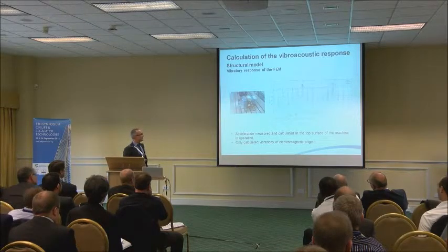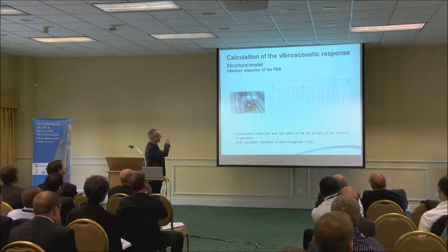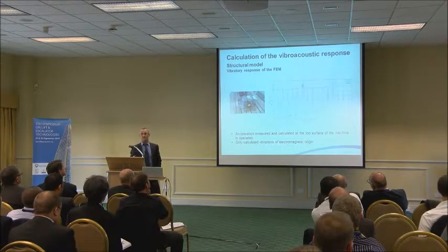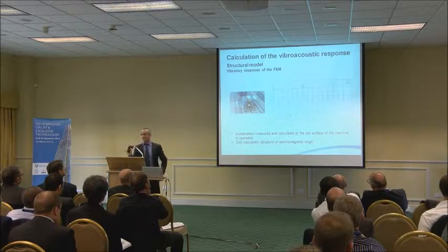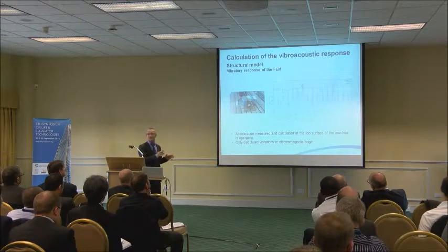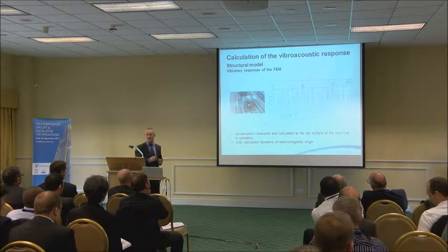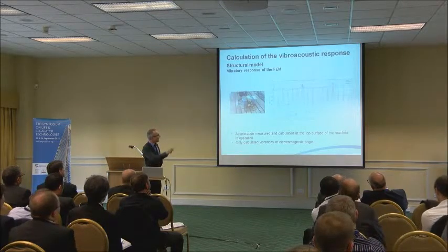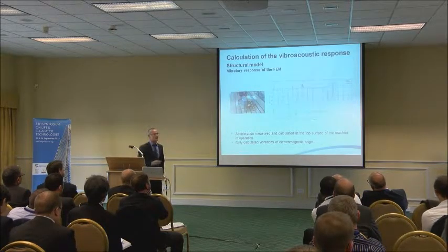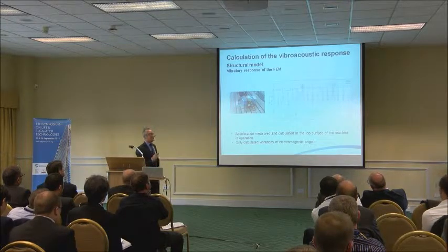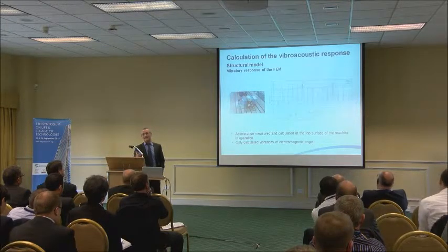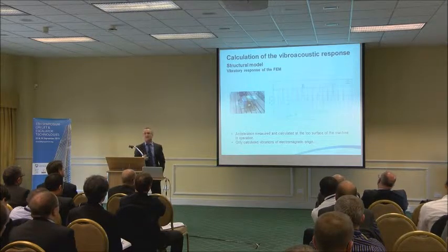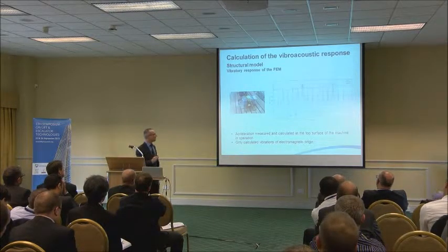And we see the picture there, where we see in blue the measured vibration. It is the whole vibration, not only that due to the electromagnetic reasons, but also the mechanical one. So actually we are measuring all, of course. And then we have in green and in red, respectively, that calculated by the FEM model and by the analytical models. I will talk later on in the next slide a little bit on the analytical models.